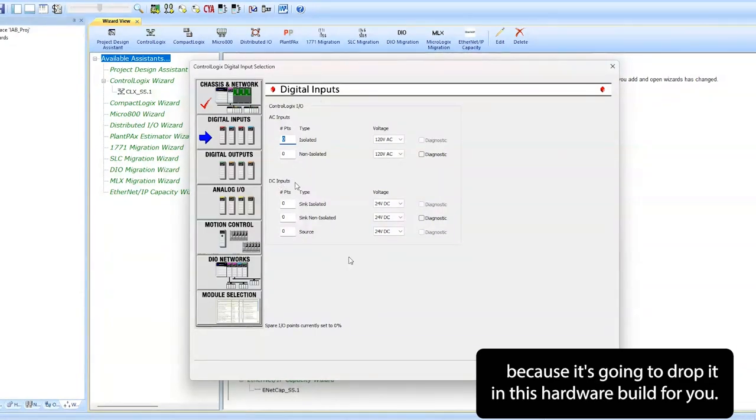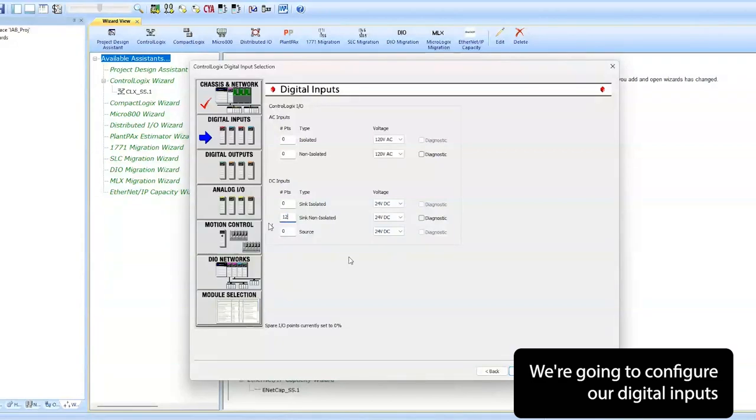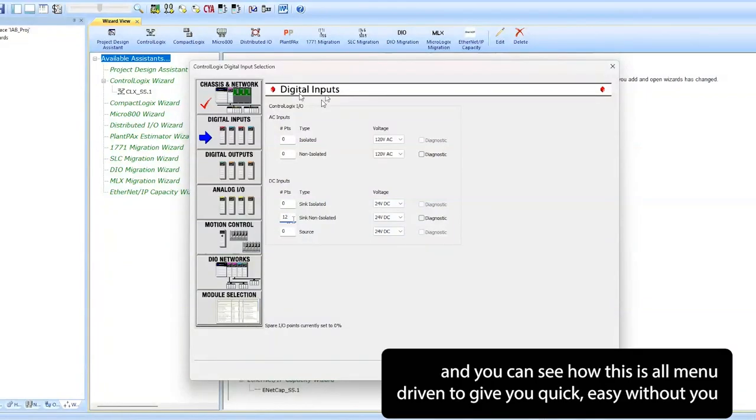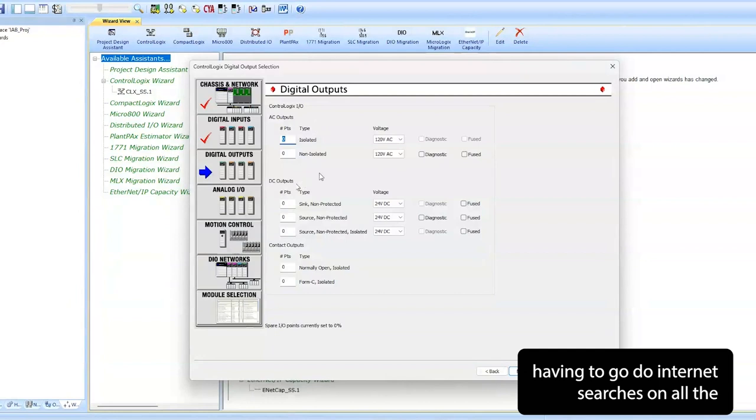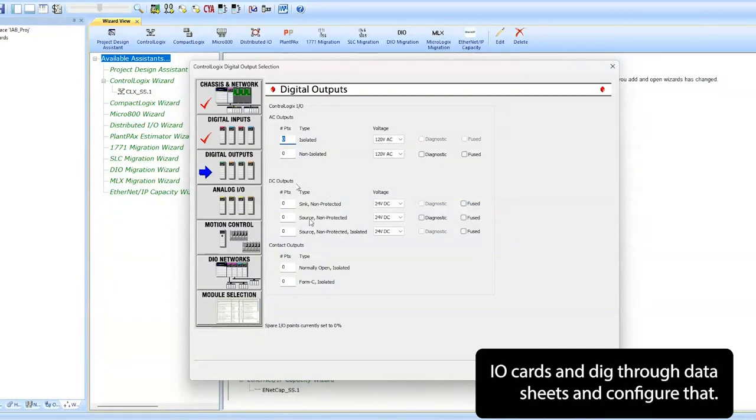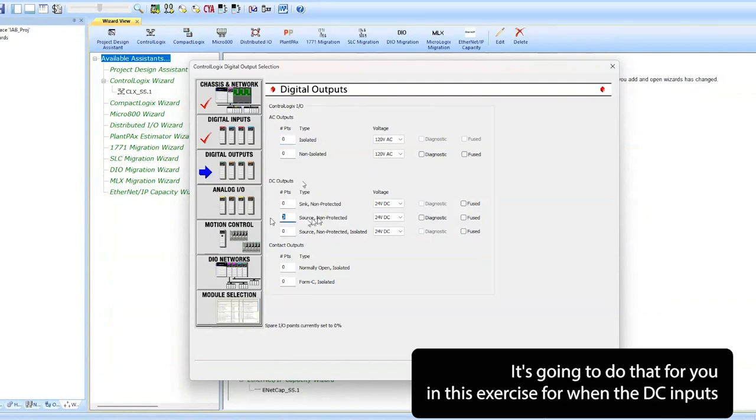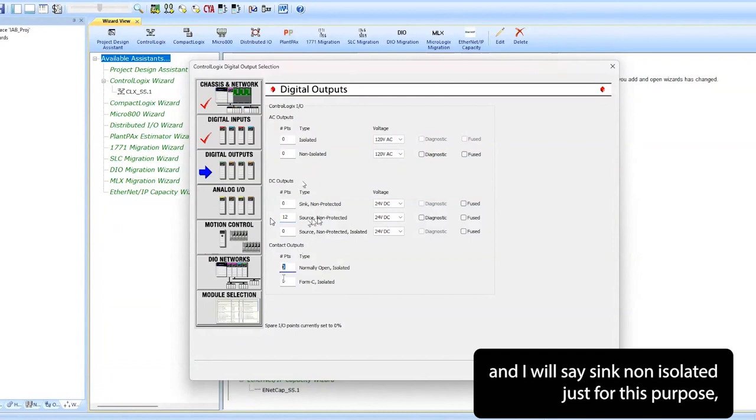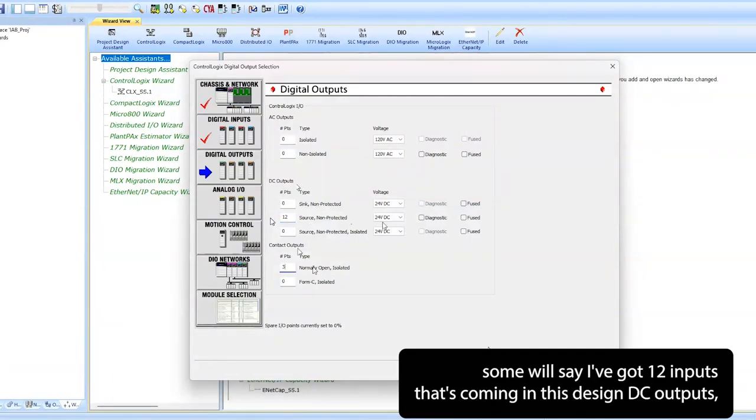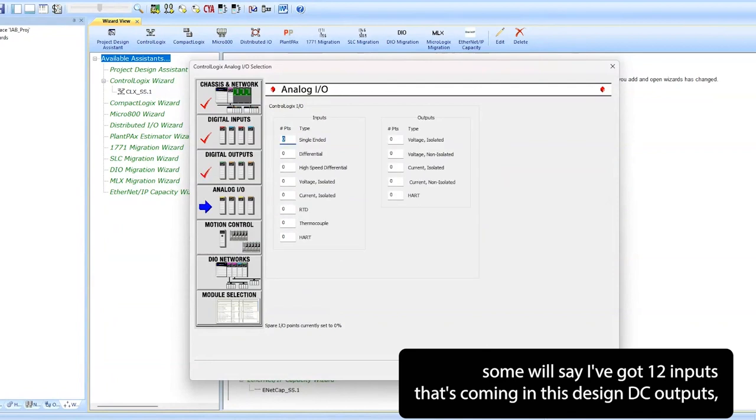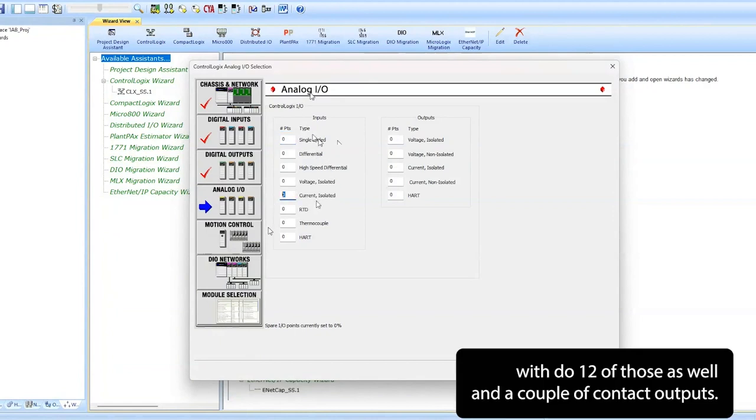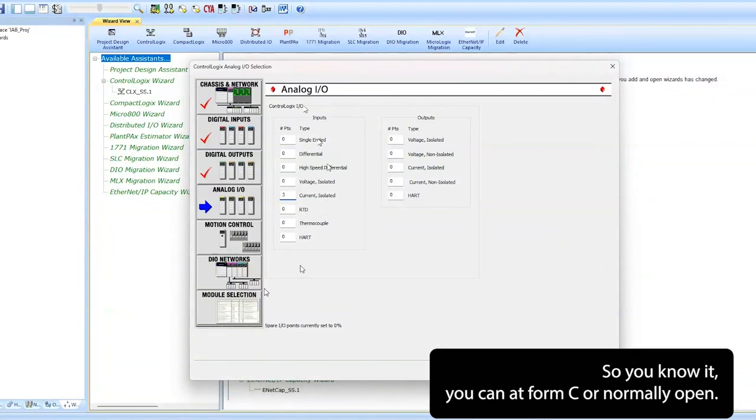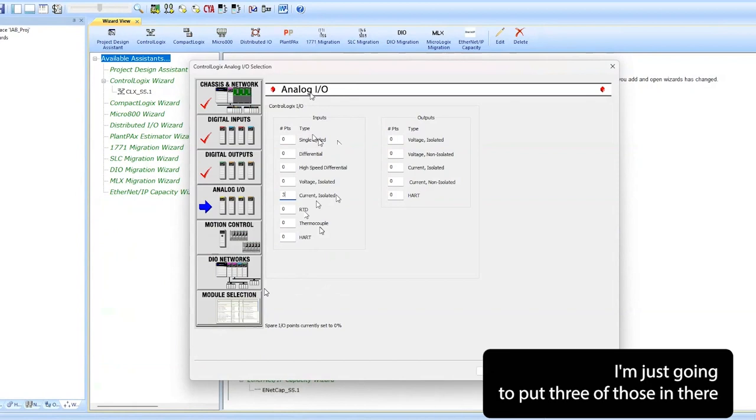We're going to configure out digital inputs and you can see how this is all menu-driven to give you quick, easy configuration without you having to go do internet searches on all the I/O cards and dig through data sheets. It's going to kind of do that for you. In this exercise we're going to do DC inputs and I'm going to say a sink non-isolated. I'm going to say I've got 12 inputs that's coming in this design. DC outputs, I'm going to select source non-protected 24 volts. We'll do 12 of those as well. And a couple of contact outputs. You can have Form C or normally open, I'm just going to put three of those in there just so you see how the cards are dropped into this hardware.